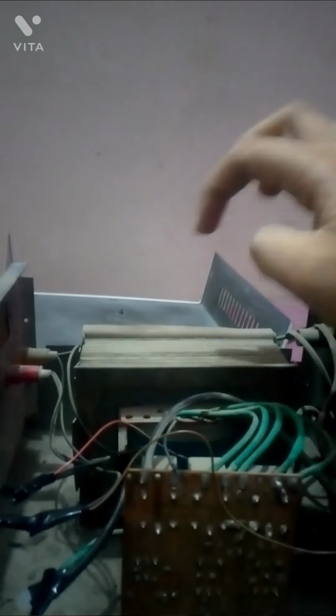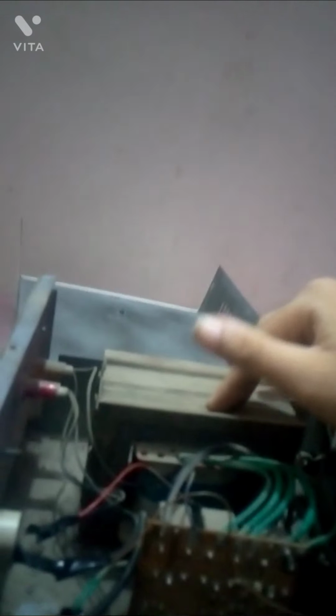This is a stabilizer, also known as a switch stabilizer, or auto transformer, 1600 watt. It contains a control card and a transformer, known as an auto transformer. It has only a primary winding, not a separate secondary winding - the secondary is part of the primary. That's why it is not isolated from mains. If you plug this thing in and touch just one output terminal, you will get an electric shock, because there is no insulation between input and output.